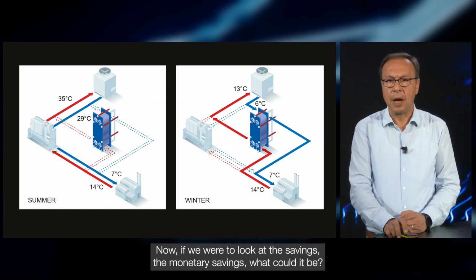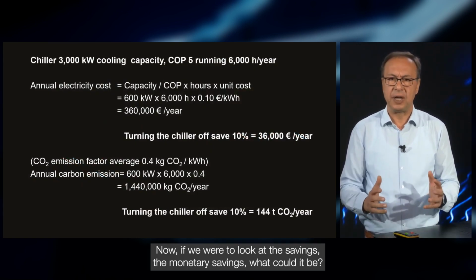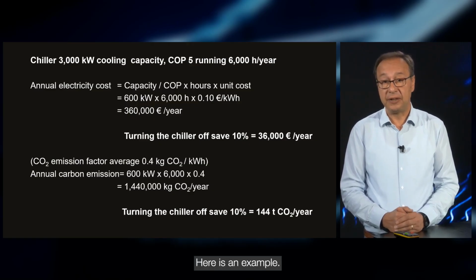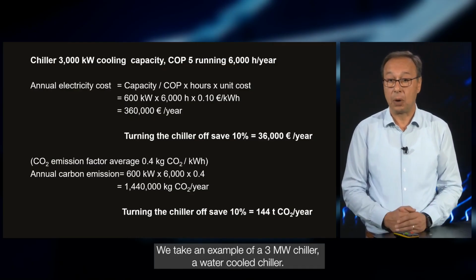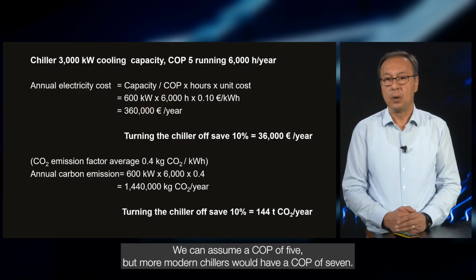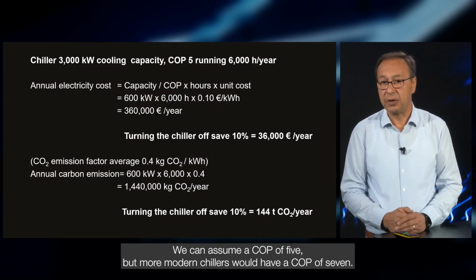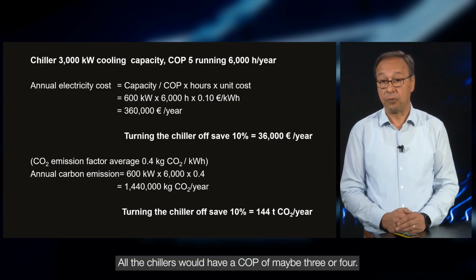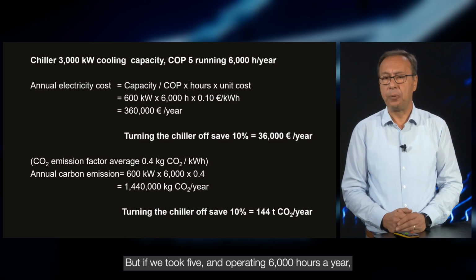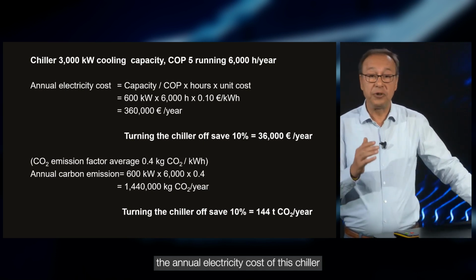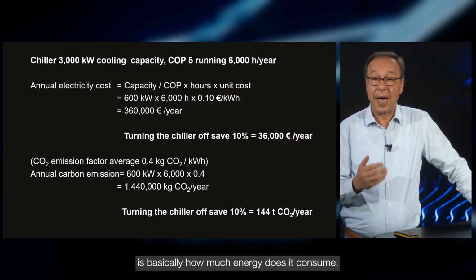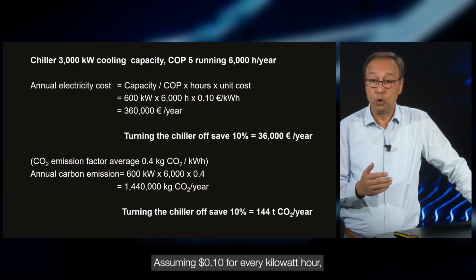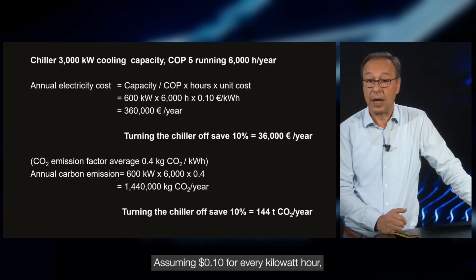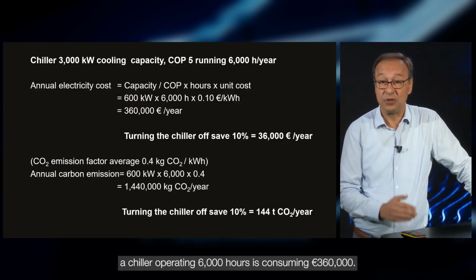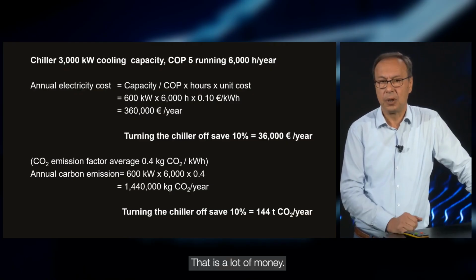Now, if we look at the monetary savings, here is an example. We take a 3 megawatt water-cooled chiller. We can assume a COP of 5, but more modern chillers would have a COP of 7, and older chillers maybe 3 or 4. If we take 5 and operation of 6,000 hours a year, the annual electricity cost is based on how much energy the chiller consumes. Assuming 10 cents for every kilowatt hour, a chiller operating 6,000 hours is costing 360,000 euro. That is a lot of money.